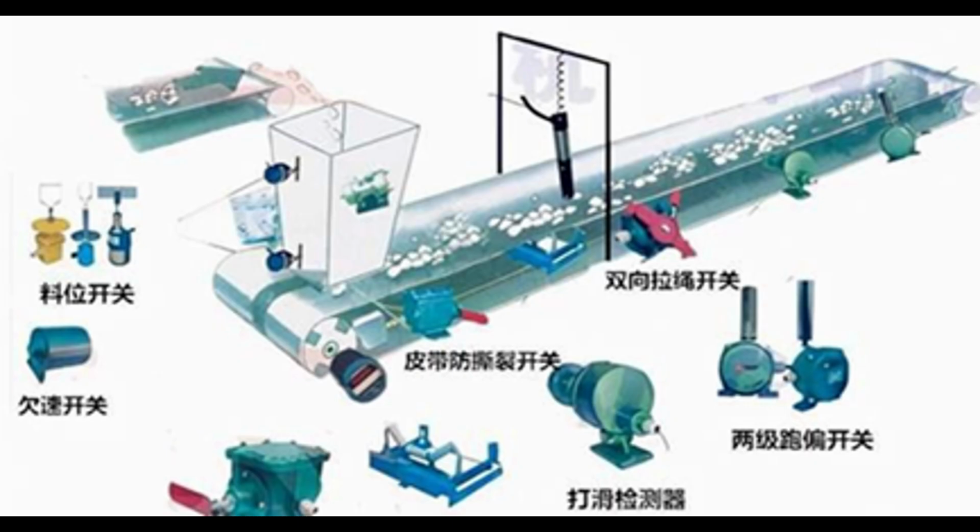2. Anti-slip protection device. It is a device that detects the speed change of the conveyor belt to check whether the drive pulley and the conveyor belt have slipped. In the normal operation of the conveyor, when the belt speed is reduced to a certain value, the slippage and low speed alarm signal occurs, and the automatic shutdown instruction is issued after the driving drum speed is lower than 70% of the normal speed for a certain time.